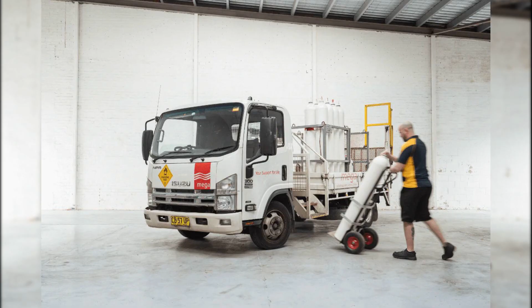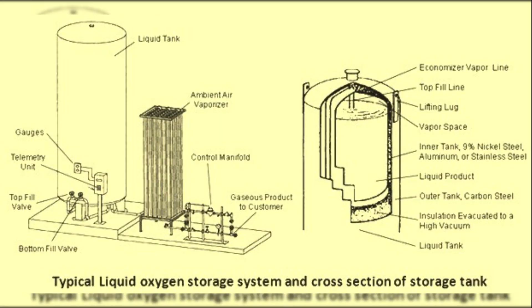The way oxygen is stored, transported, and delivered depends entirely on how much is needed and where it will be used. In large industrial operations, oxygen is most commonly stored in its liquid form. Liquid oxygen occupies far less volume than gaseous oxygen, making it ideal for large-scale storage and long-distance transport. To keep oxygen in a liquid state, it must be maintained at extremely low temperatures. This is achieved using specially designed cryogenic tanks with thick insulation that minimizes heat transfer from the environment. These tanks are not actively cooled. Instead, they rely on insulation to slow down heat flow. A small amount of oxygen continuously boils off, which is normal and carefully controlled.